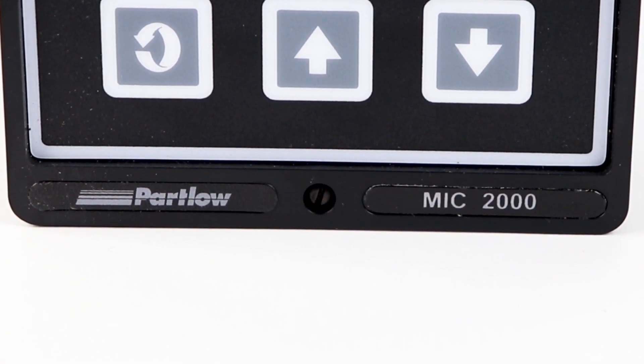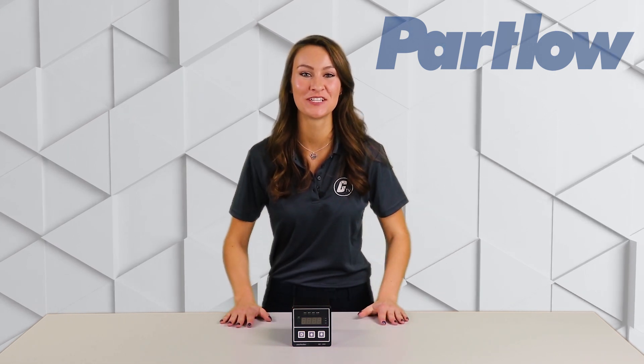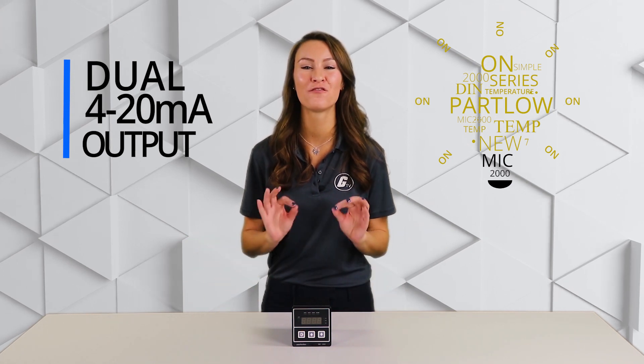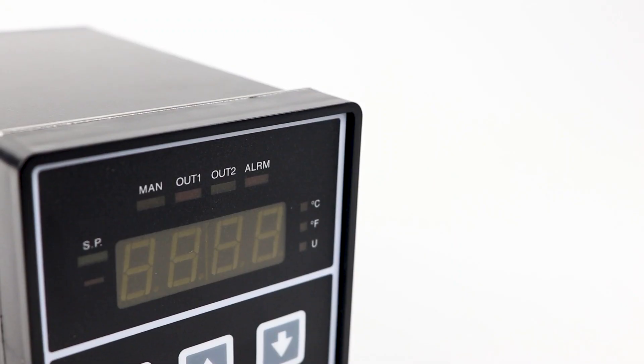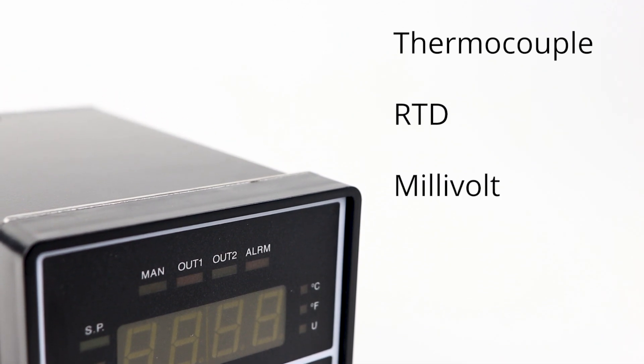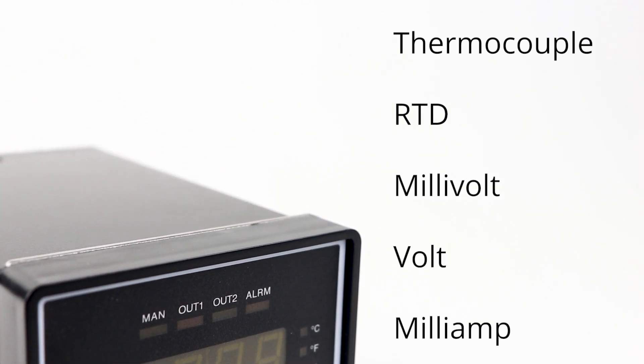Partlow's MIC 2000 Series Temperature Controller is a single-loop, quarter DIN controller that is capable of controlling a variety of processes ranging from simple on-off operation to dual 4-20 milliamp output with full PID. Inputs include thermocouple, RTD, millivolt, volt, and milliamp.